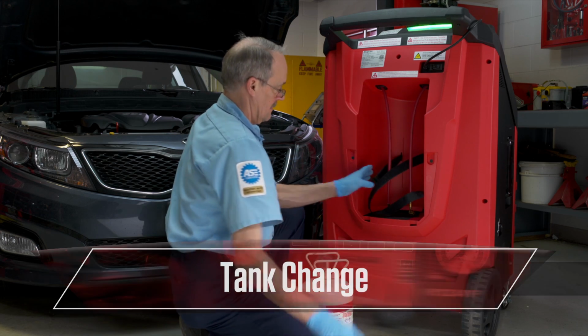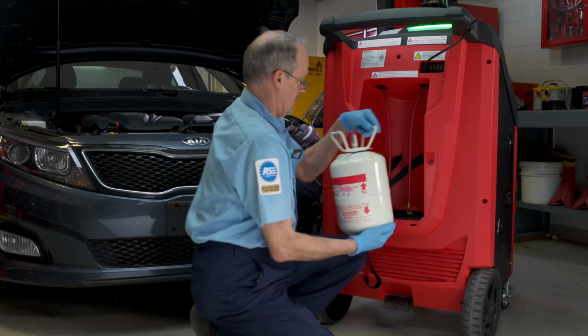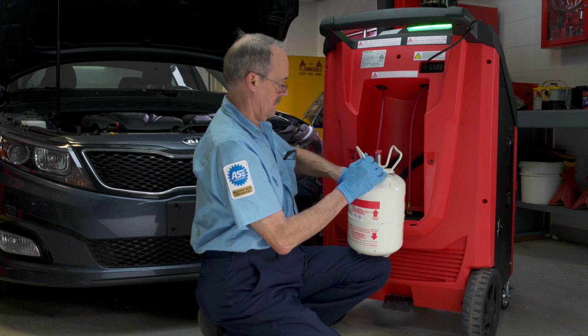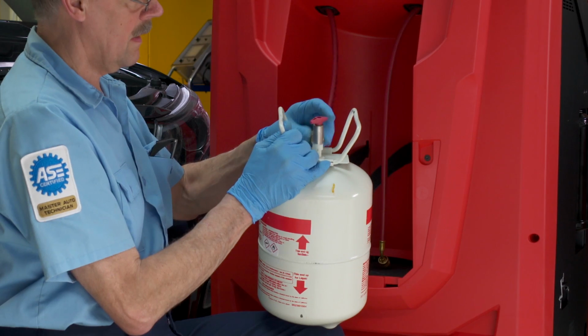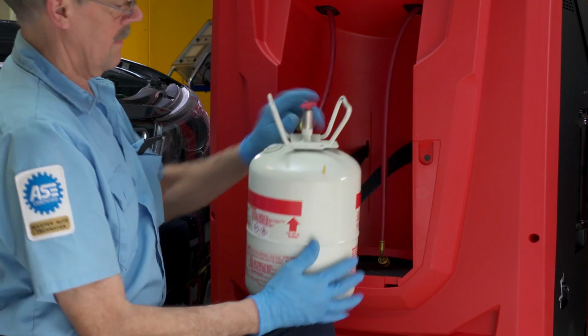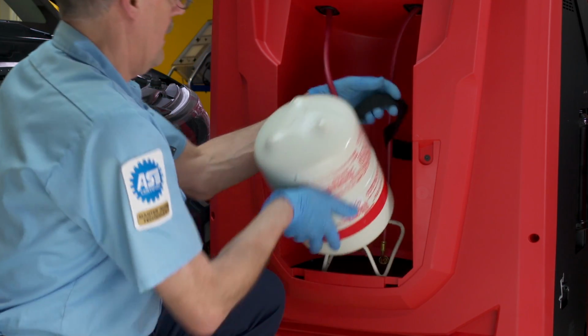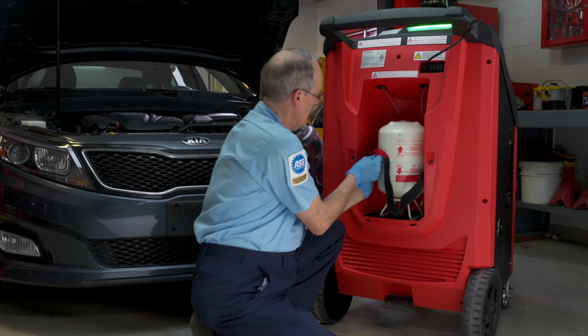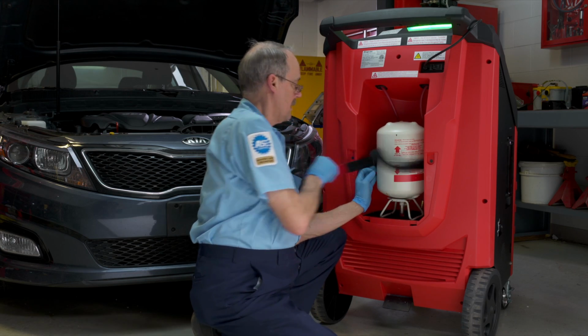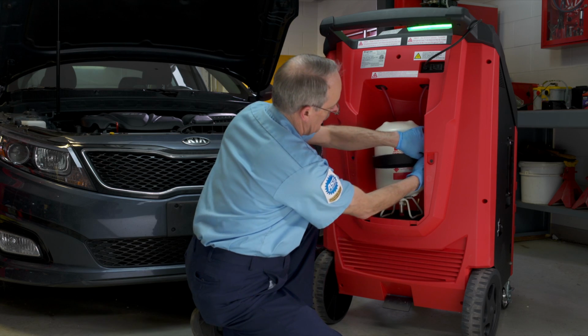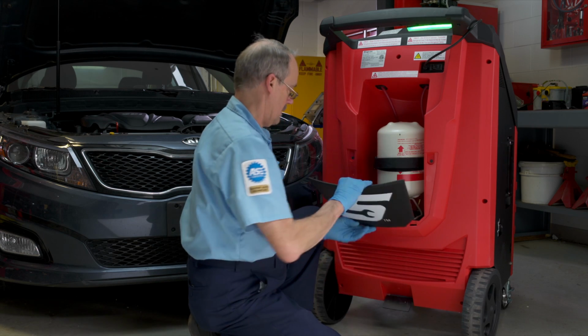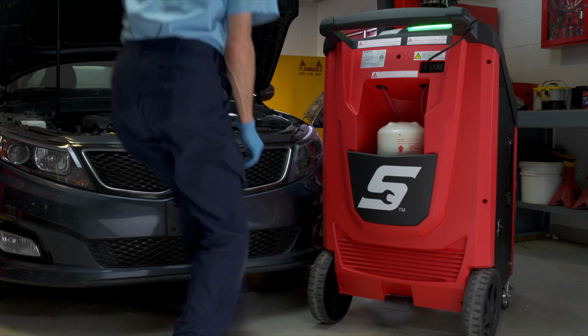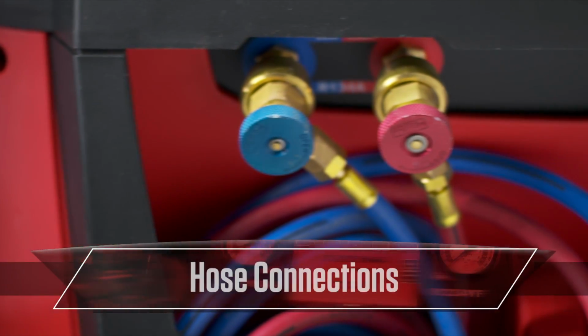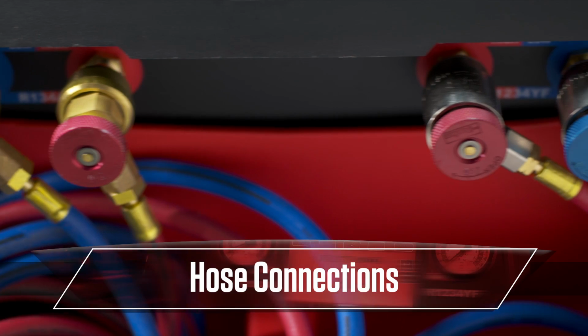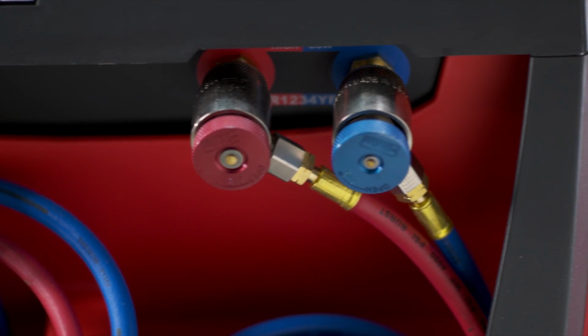To make a tank change, remove the cover from the back of the machine. Attach the appropriate hose that matches the type of refrigerant you're adding. Turn the tank upside down. Strap the tank in place. Finally, replace the cover. Attach hoses to the front of the machine as shown.